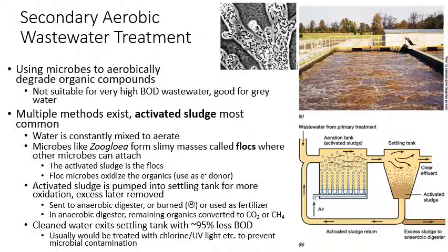After the mixing tank, you would pump all that water with the activated sludge into a settling tank, and let it sit there. The sludge is heavier than the water, so it's going to sink to the bottom of the tank. Meanwhile, it's still got plenty of oxygen in the water, so you're still having metabolism going on in that sludge. It is still activated sludge.